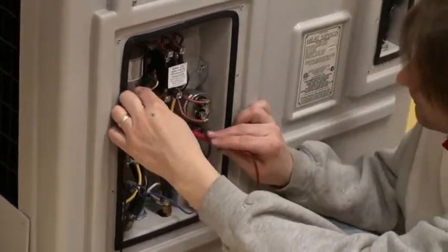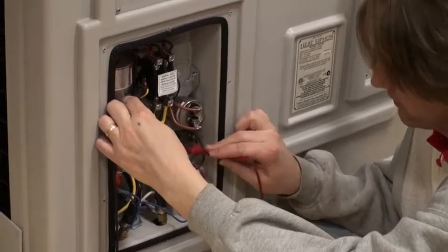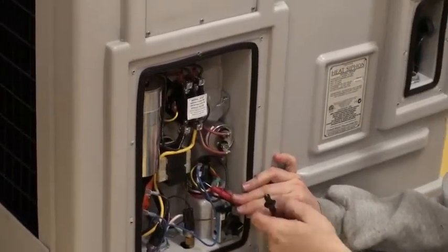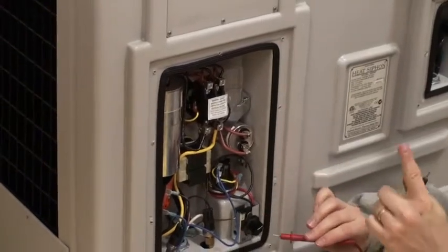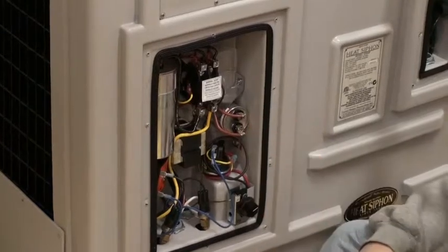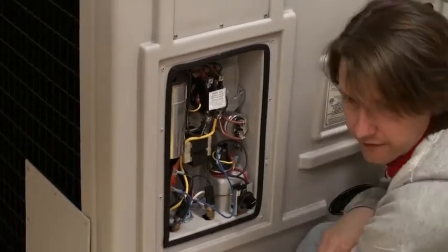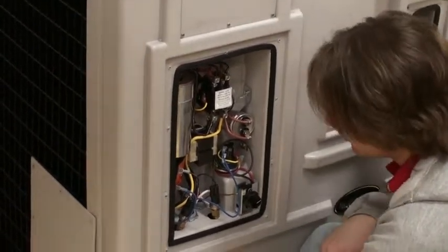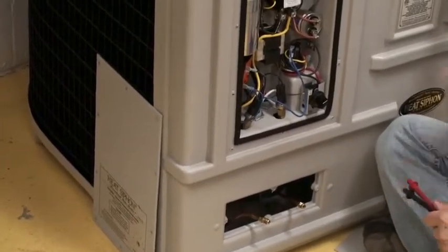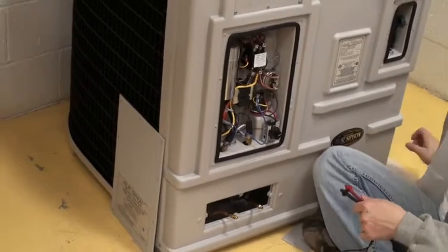So you go to the other side, and if you don't have it, then it's here. And you can look visually, turn the pump on and look. Is that thing engaging? That's that piston hitting the nipple of the switch. And then you know where to go from there. Is this clear tube connecting? Is there something clogging the filter of the pump?